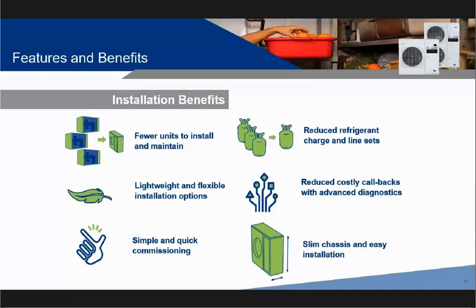When it comes to the fewer units, you also have reduced refrigerant charge and line set benefits. So I'll talk about the field test site that we're going to share today, and they were actually able to reduce the refrigerant charge by 50% by eliminating condensing units and consolidating line runs. And then with our advanced diagnostics, we make sure that the unit's running properly the first time, trying to save that contractor the costly callbacks. So with the diagnostics, if they set the unit up and there's something wrong, it's going to immediately give them an error, and they can see what that error code means and troubleshoot on the spot and make sure that it's running properly before they leave.